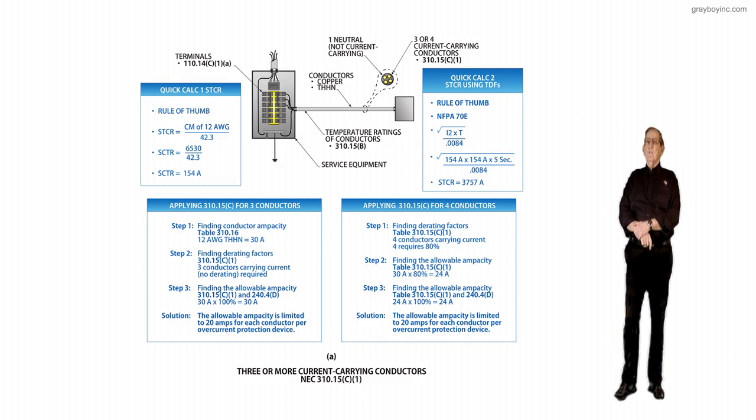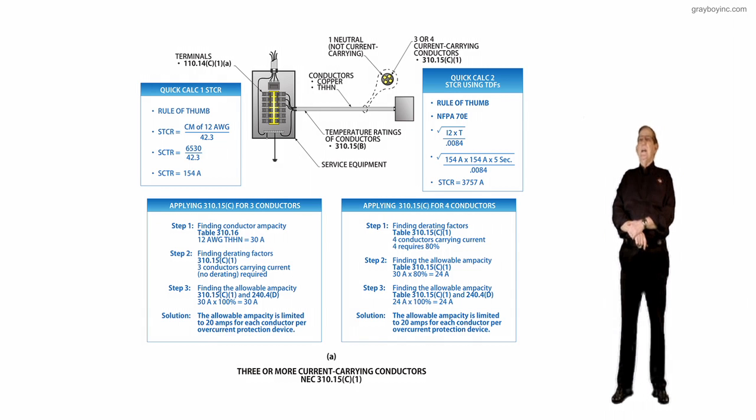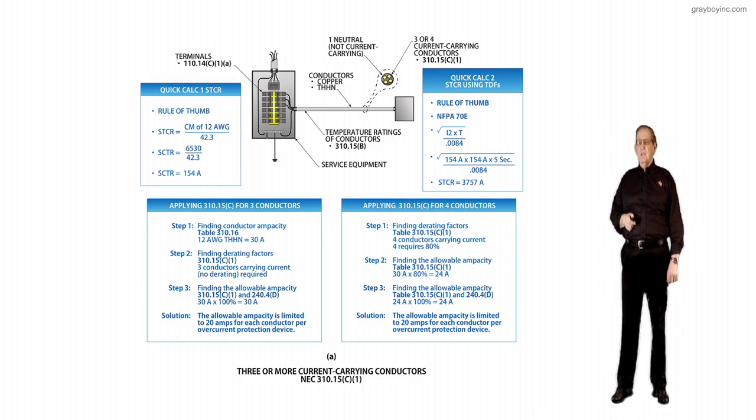That's a good rule of thumb that engineers have used for a long time. Now notice if you had 4 current carrying conductors instead of 3, you don't use method 1, you go to method 2. In table 310.15 C1, 4 conductors carrying current requires 80%. In other words, your neutral is considered a current carrying conductor.